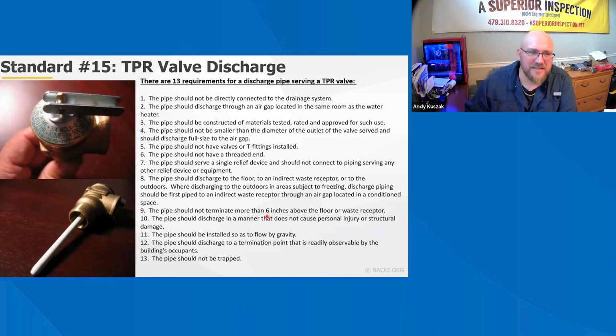So actually, I'm going to comment on these as we go through them. So the pipe should not be directly connected to the drainage system. That is to ensure bacteria does not travel up the waste system and up into the temperature pressure relief valve and into the water heater. So the same thing goes for having an air gap from the discharge pipe into a drain. You want to make sure that there is no possibility for bacteria or any organisms that are in the sewer or in the waste system to jump from the waste pipe into the potable water system.